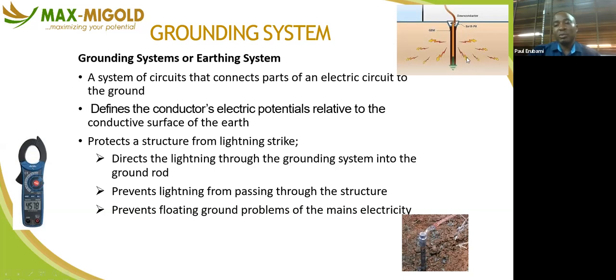Copper is mostly used because copper has the tendency of conducting current easily. So don't compromise the standard. Don't say, I want to use a lesser quality. No, that is the heart of your installation, earthing. So we lay emphasis on earthing, and you have to ensure you carry out a regular test on it. I recommend two tests in a year, the rainy season and the dry season. In the rainy season, the current flowing through this earth is so huge, and I told you earlier that current comes with heat.